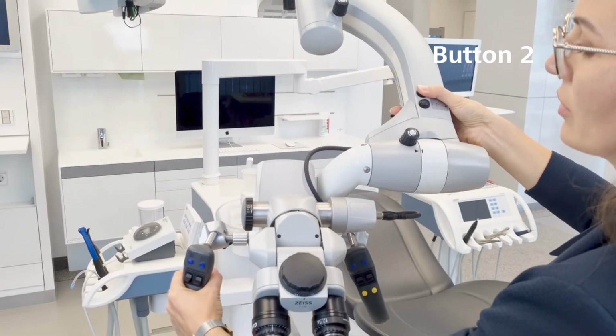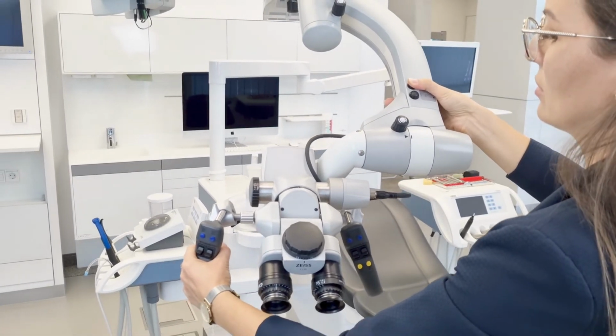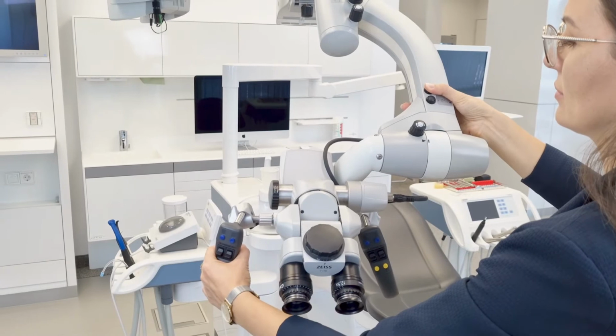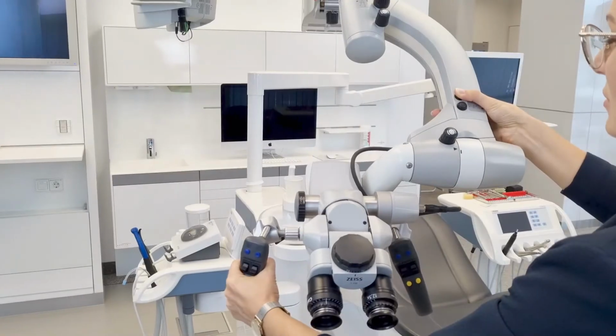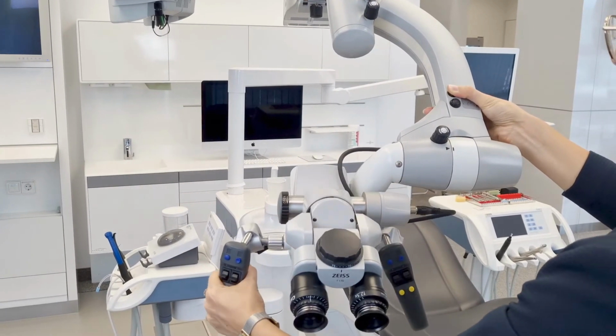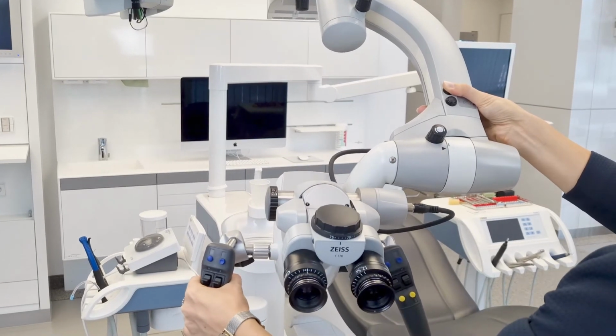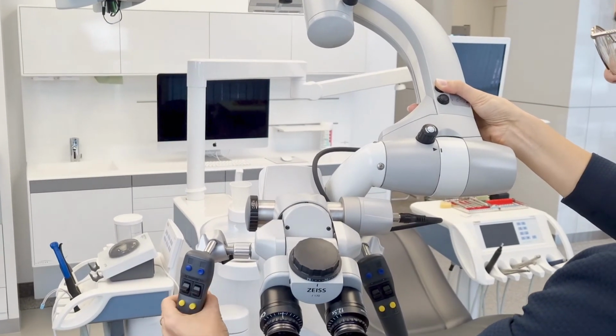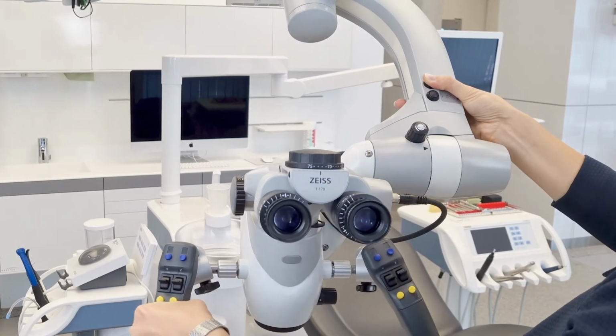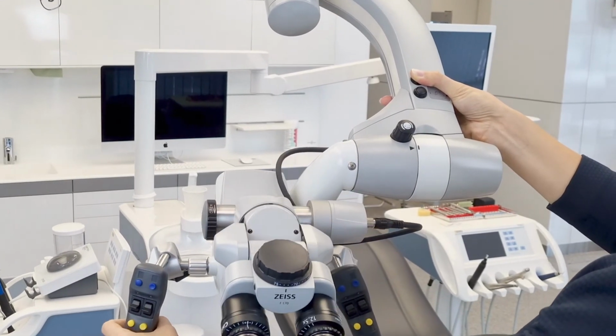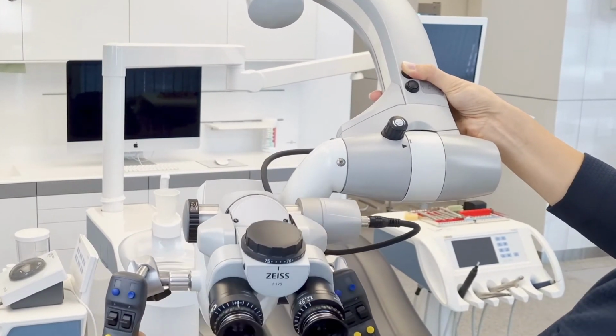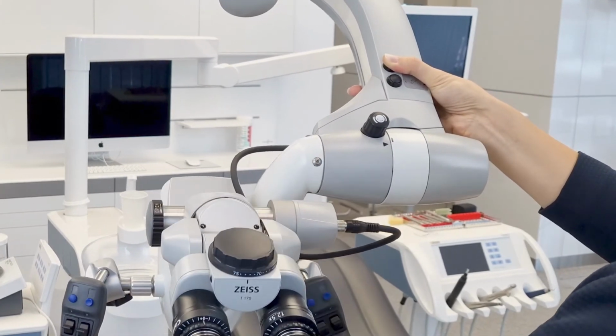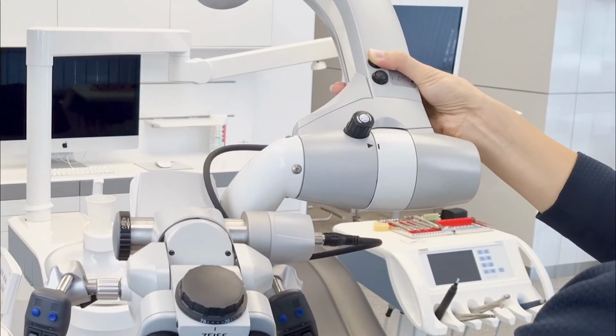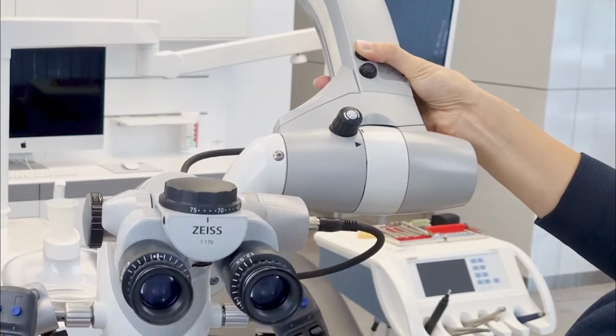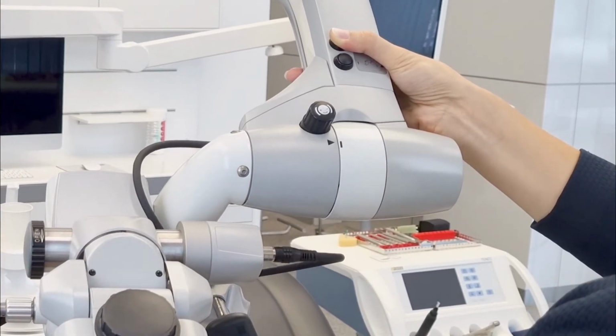While pressing button 2, move the surgical microscope evenly back and forth by approximately 2 mm until the surgical microscope body has been coupled. This is the case if the white ring moves along when the surgical microscope is turned. Continue pressing button 2 until the surgical microscope remains balanced in each position. Depending on the accessories attached, this may take some time, approximately 1 minute or longer.